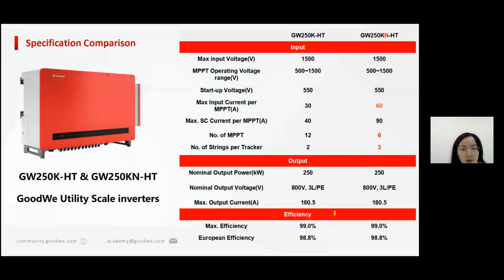Here are the specifications of the HT series. So actually we have two main products, which are the 250K and 250KN. The main difference is that they have different MPPT numbers, and the maximum input current is totally different. So the KN will have an even larger DC input current. For each MPPT, it can have a maximum of 60 ampere input. So it can definitely adapt to the trend of high current PV modules. And for 250K, it can be used directly for modules like 182 millimeter PV modules.